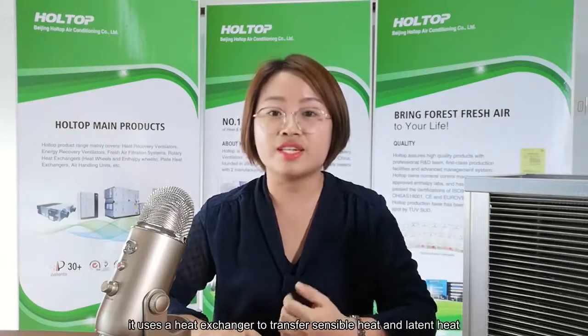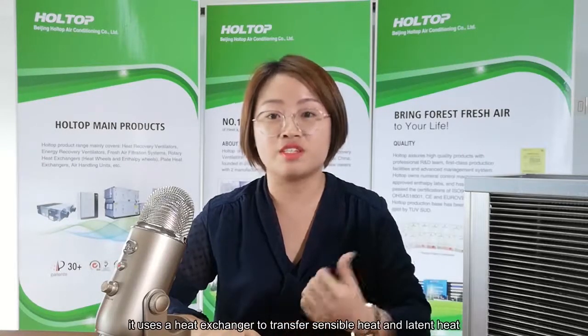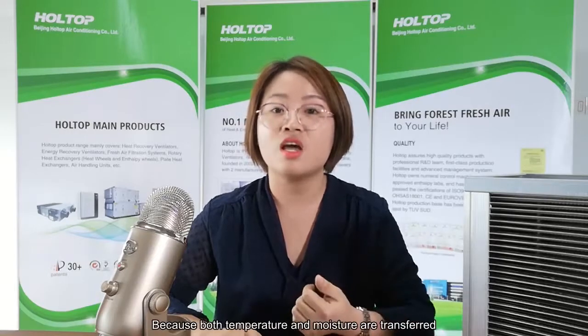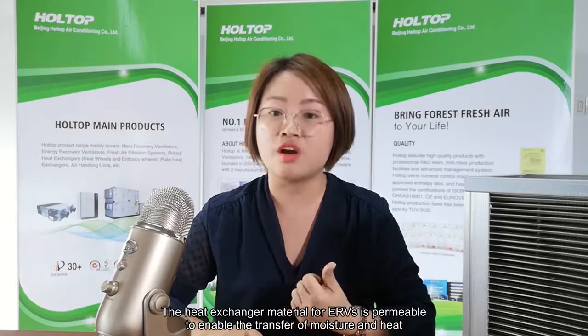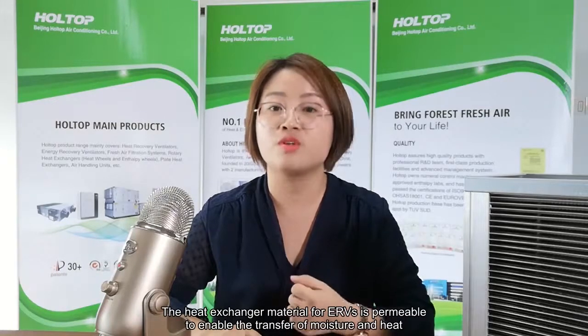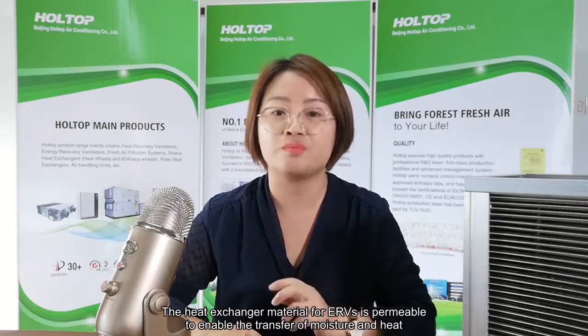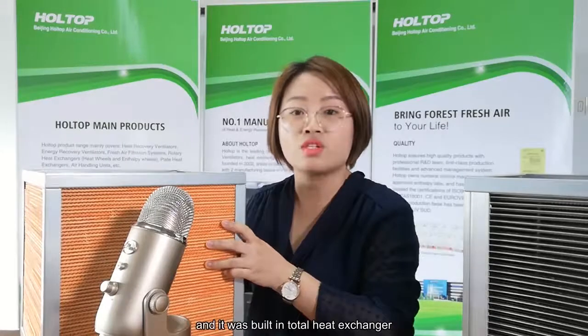Well, ERV stands for Energy Recovery Ventilator. It uses a heat exchanger to transfer the sensible heat and the latent heat. Because both the temperature and the moisture are transferred, the ERV is considered a total enthalpic device. The heat exchanger for ERV is permeable to enable the transfer of moisture and heat. For example, Holtop ERV, with airflow ranging from 150 to 20,000 cubic meters per hour, is built with this kind of total heat exchanger.